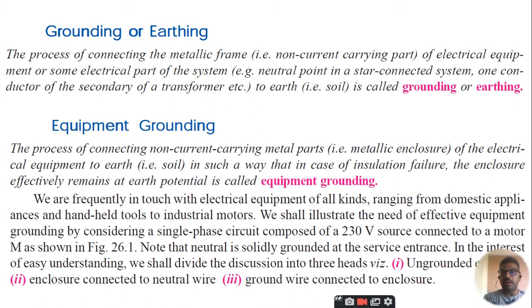So there is a phenomenon known as grounding or earthing. The process of connecting the metallic frame, that is the non-current carrying part. You may also see a cupboard type of panel where the non-current carrying part, say for example the metallic body of the cupboard, is connected with the ground with some fins, or we can say a metallic conductor, which is to be connected with the ground for safe operation. So the process of connecting the metallic frame of the electrical equipment or some electrical part of the system, that is the neutral point in the star connected system, after having the general discussion of three-phase system, you may now be able to know what a star connected system is and what the neutral is in that, to the earth is called grounding or earthing.